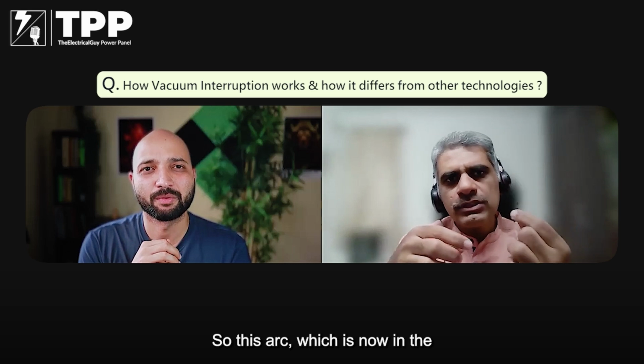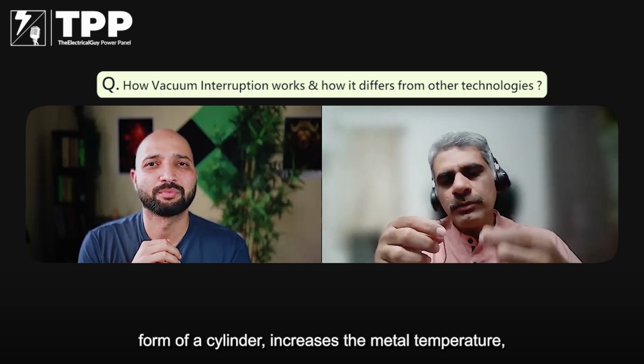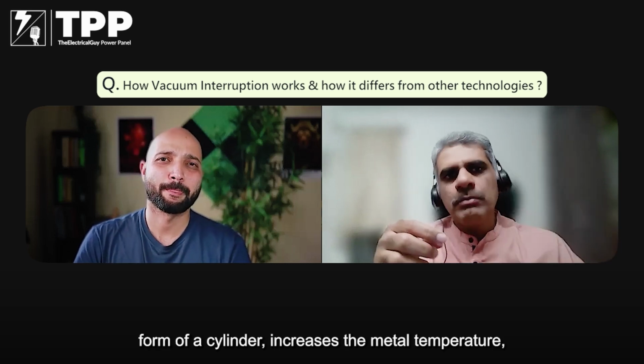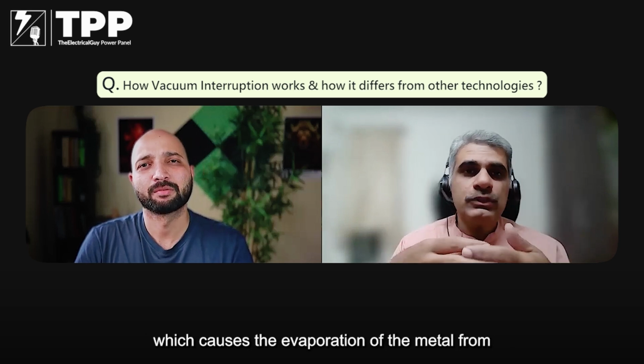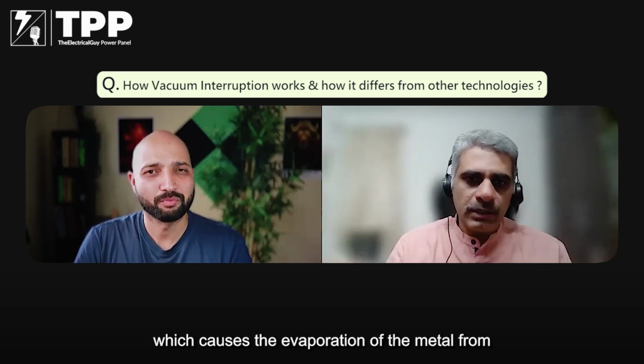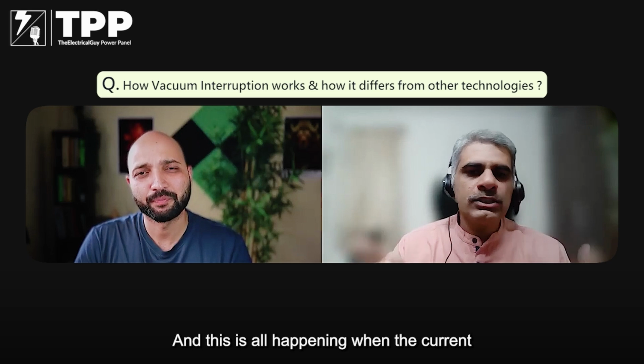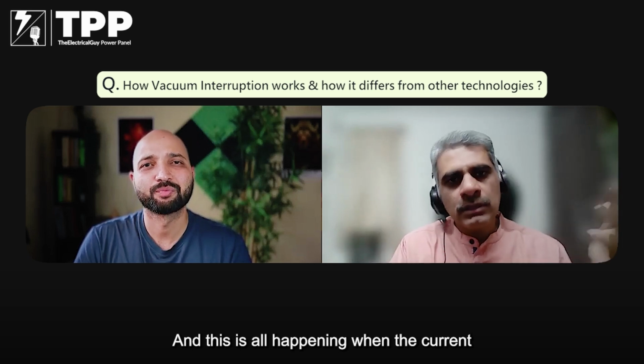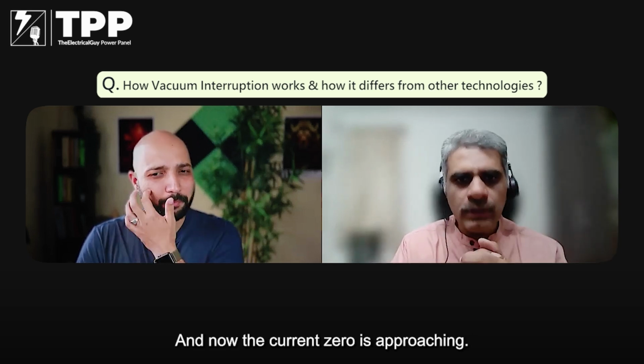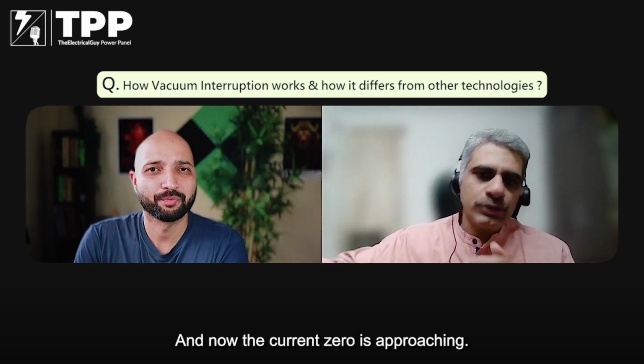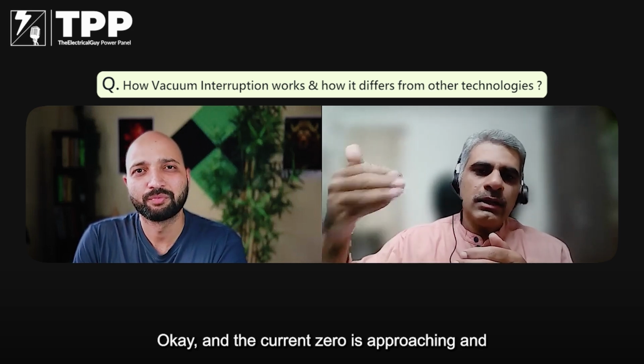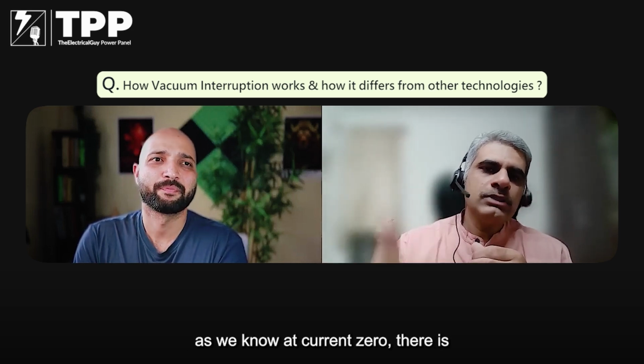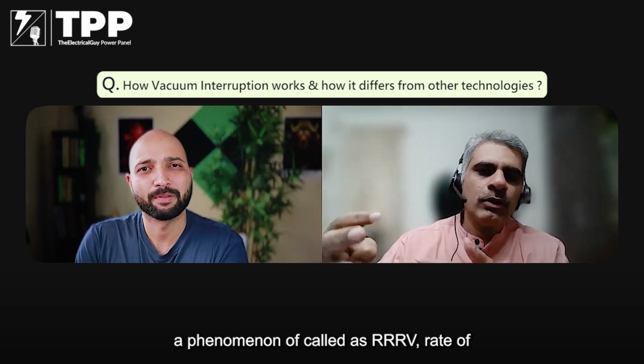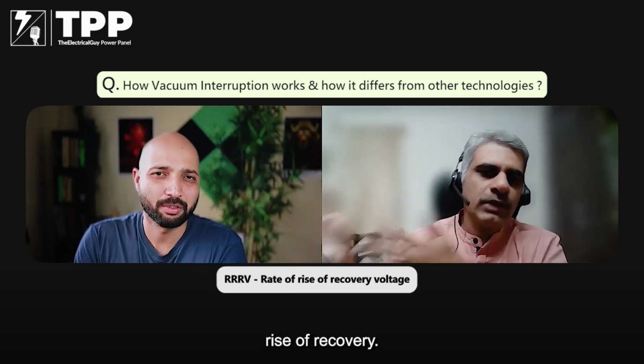So this arc, which is now in the form of a cylinder, increases the metal temperature, which causes the evaporation of the metal from the contacts. And this is all happening when the current is still there. Okay, the current is still flowing, and now the current zero is approaching. And as we know, at current zero, there is a phenomenon called RRRV, rate of rise of recovery voltage.